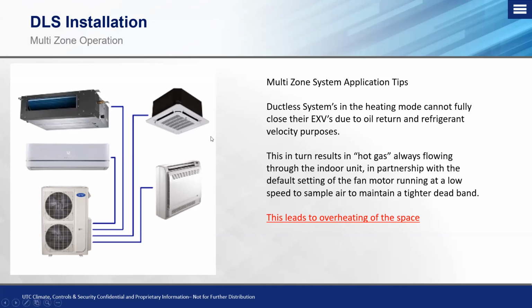Okay, now if you look on the picture here, you'll see if this high wall unit was in an active call for heating, the other units are going to have hot gas circulated through them, and that, again, is to circulate a minimum amount of return oil back to the compressor. They have to maintain a minimum position. The EXVs will never be fully shut. And this is what leads to the overheating of the space.